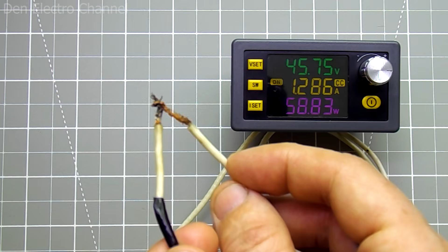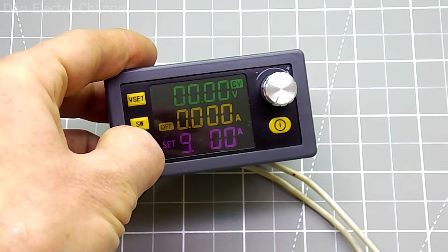Something similar is happening here, only the problem is a little more complex. Current regulation is triggered according to your setting, but it doesn't happen immediately. Let's take a look at this. The voltage at the converter output is currently 5 volts. A multimeter set to 10 amps is connected to the converter output, and I'll use it to short-circuit the converter wires.